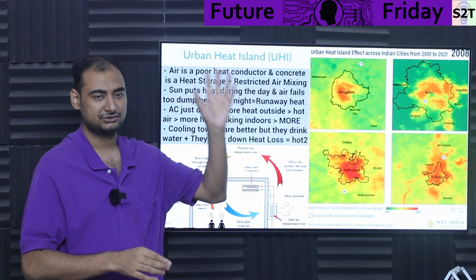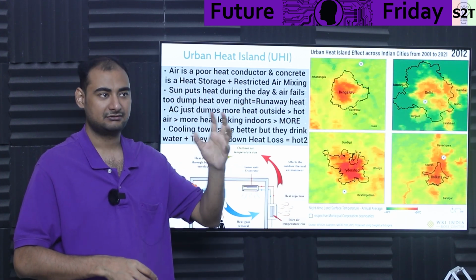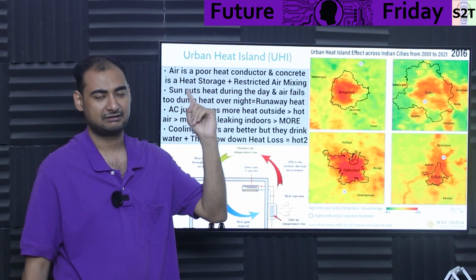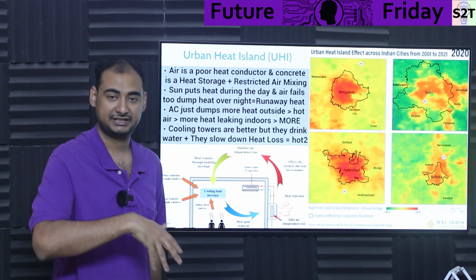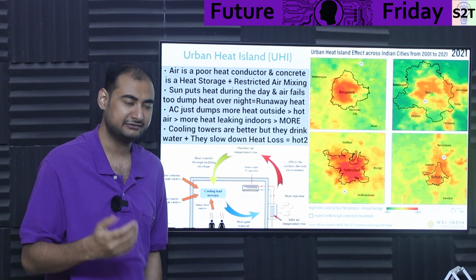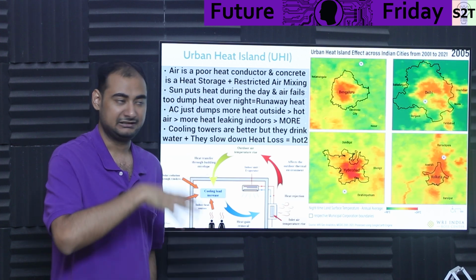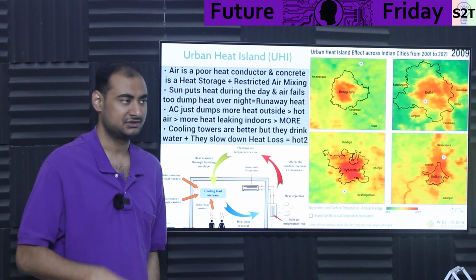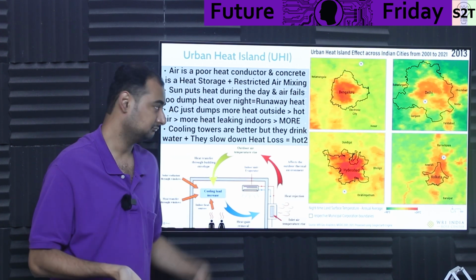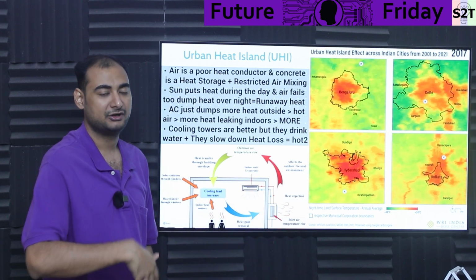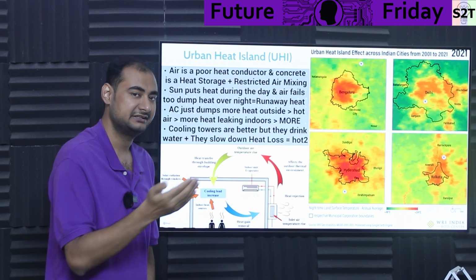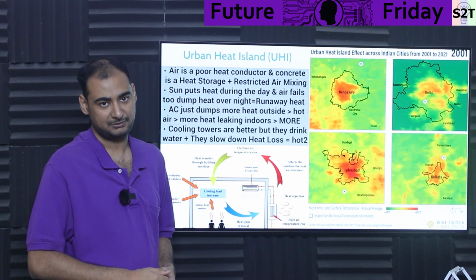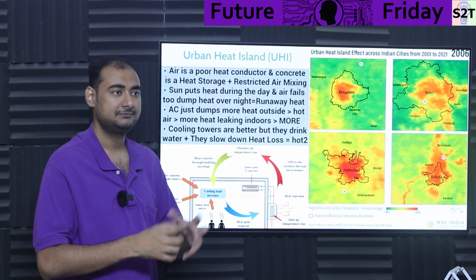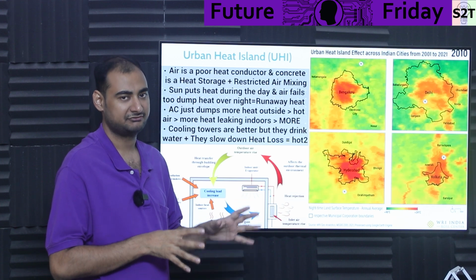So that water goes into a cooling tower. In that tower, it could generally be a closed loop scenario. But to cool that coil, because air cannot take enough heat away quickly enough, we spray them with water. If it's cold enough, cool water recirculates. But if it's not cool, the water just evaporates away, which we call latent heat of vaporization, meaning it leaches a lot of heat away with surprisingly little amount of energy.